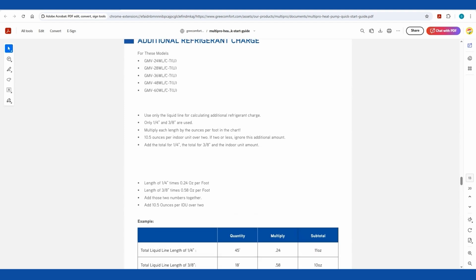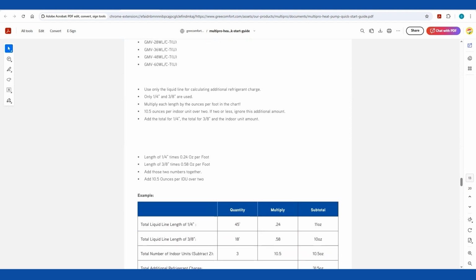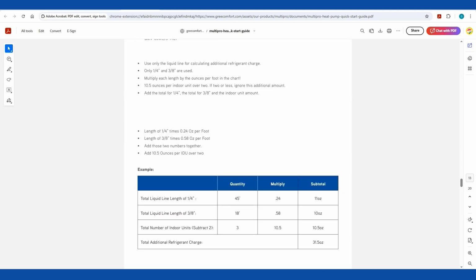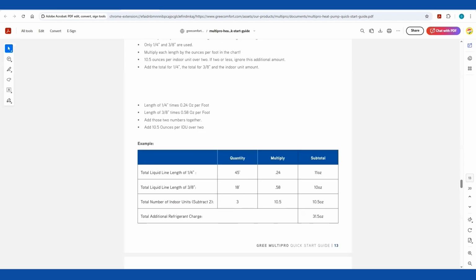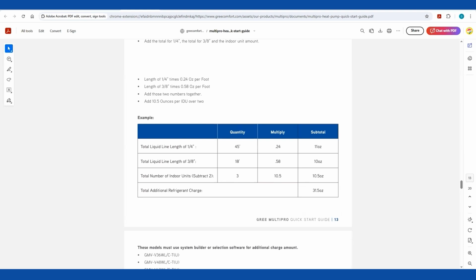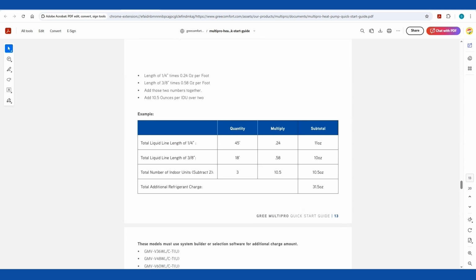Multiply each length by the ounces per foot in the chart. You need to add 10.5 ounces per indoor unit over 2. If 2 or less, ignore this additional charge amount. Add the total for the 1/4 and the 3/8 and the indoor unit amounts. So let me give you an example. So let me give you your charge amounts first. Length of a 1/4, use 0.24 as your multiplier. 3/8, you're going to use 0.58. Add those two numbers together, plus whatever you need for any units over 2 is 10.5 ounces.